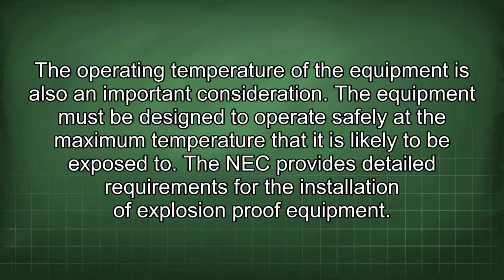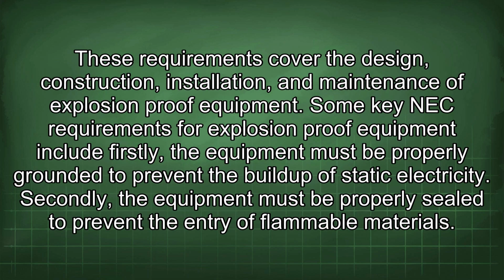The operating temperature of the equipment is also an important consideration. The equipment must be designed to operate safely at the maximum temperature that it is likely to be exposed to. The NEC provides detailed requirements for the installation of explosion-proof equipment. These requirements cover the design, construction, installation, and maintenance of explosion-proof equipment. Some key NEC requirements for explosion-proof equipment include: firstly, the equipment must be properly grounded to prevent the buildup of static electricity. Secondly, the equipment must be properly sealed to prevent the entry of flammable materials.